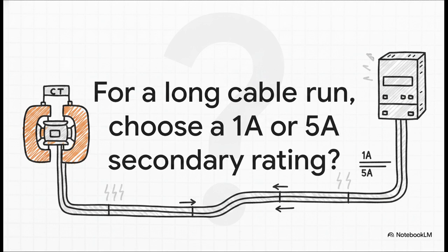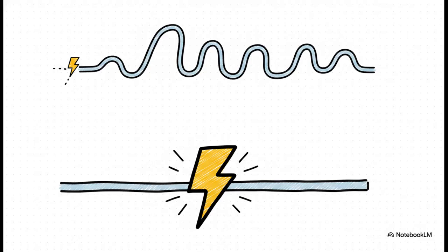Let's do a quick check to test your engineering intuition here. Think about the actual physical realities of copper wiring for a second. If you have a really long cable run from your CT way out in the switchyard all the way back to your relay panel, which secondary rating would you prefer to specify? 1 amp or 5 amps? The answer, you'd want to go with a 1 amp secondary rating.